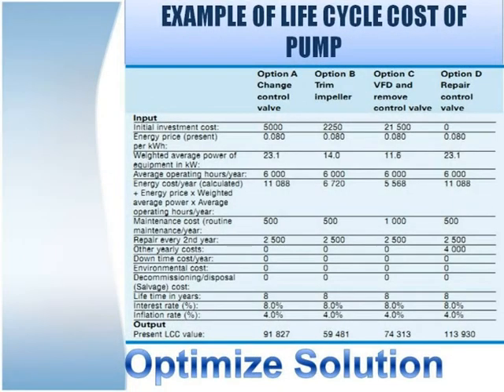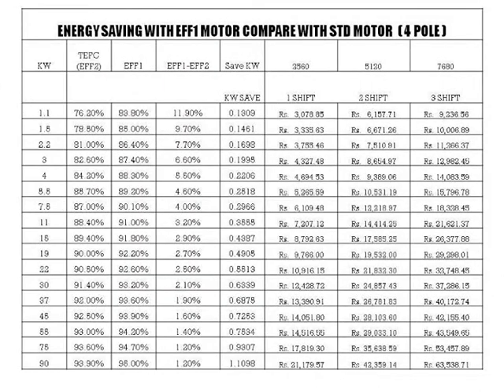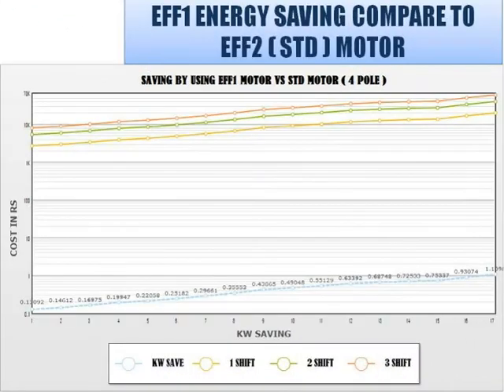There is a limitation for trimming the impeller — you cannot trim beyond 20% of the full impeller size. When should you use an EFF1 motor? Is there any saving, and how much can it be? Use an EFF1 motor compared to a standard motor for continuous operation; the payback period can be 2 years or less depending upon duty condition and size of motor.